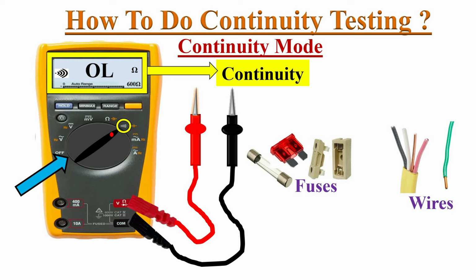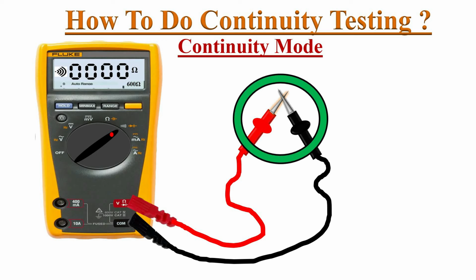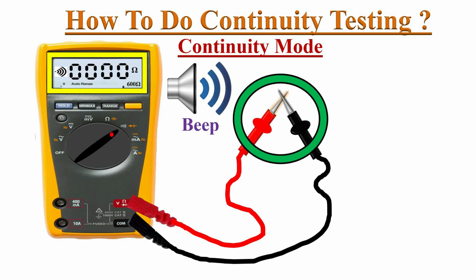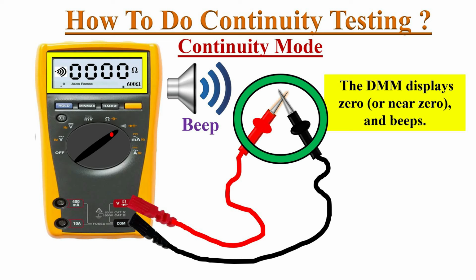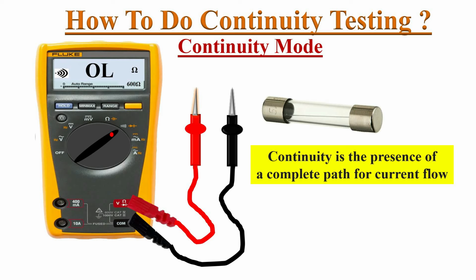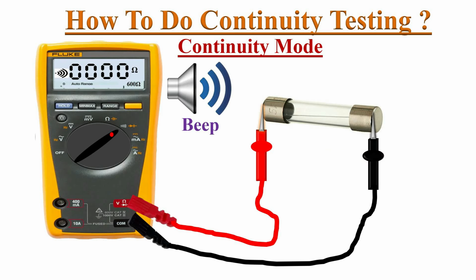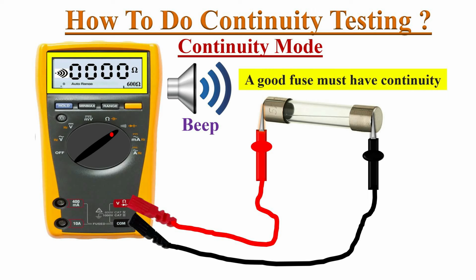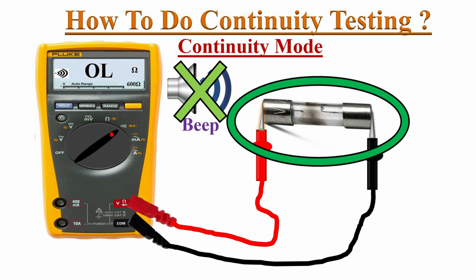Here the meter shows OL reading because there is no electrical connection between the test probes. Now touch the probes to each other. If the meter beeps or gives 0 reading, that means the meter is working fine. Now take a fuse or wire which you want to test and connect the probes to both ends of the component respectively. If the meter shows 0 and beeps, it means the path is complete and allows the flow of current. A broken or open component does not allow the flow of current.